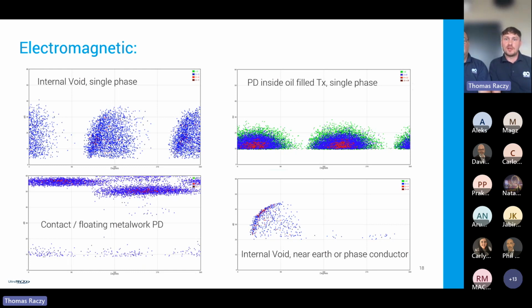Top right corner, this is a very characteristic phase resolved pattern for PD inside oil, whether that's an oil-filled transformer or oil switchgear. They typically look like those clouds of discharges, of very high intensity, hence the red color. So if you ever see anything like that while testing oil-filled assets, the likelihood is the PD is coming from inside the fluid insulation.